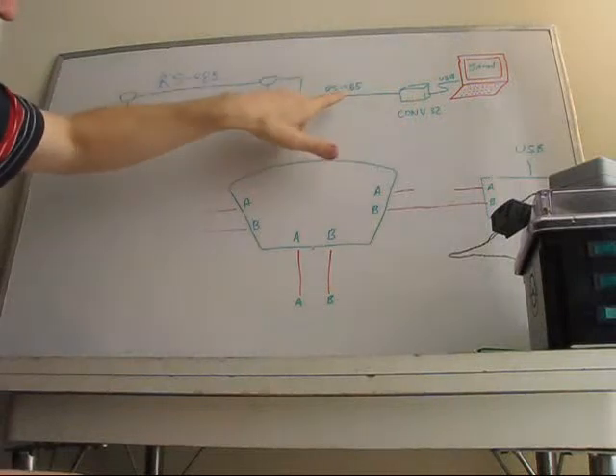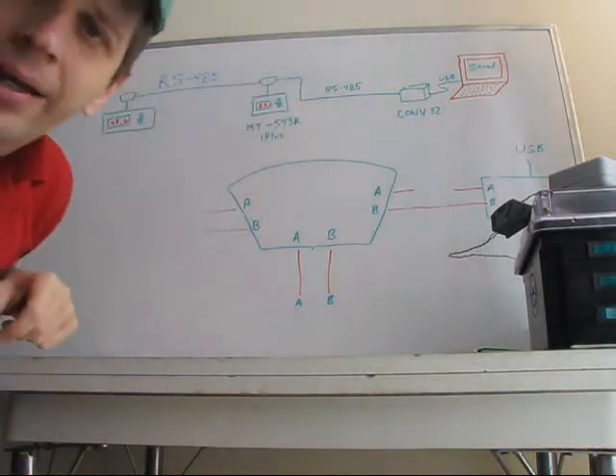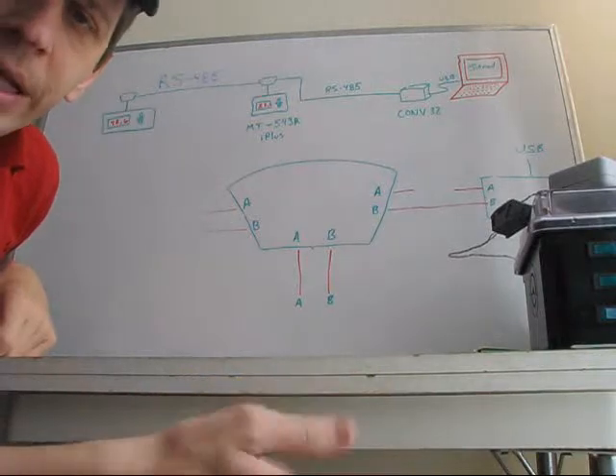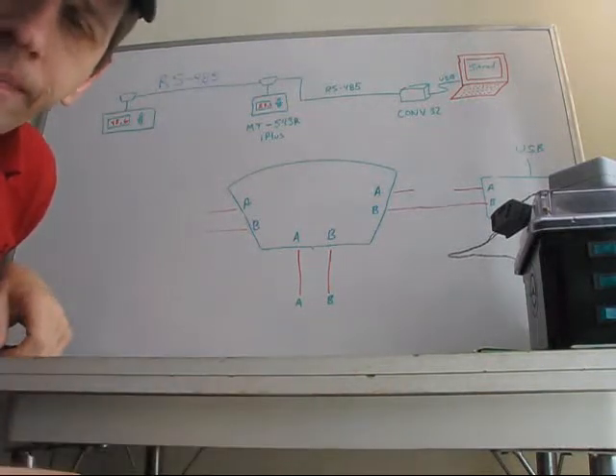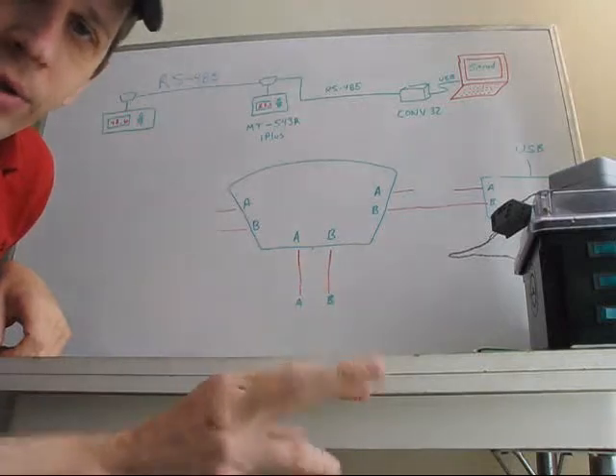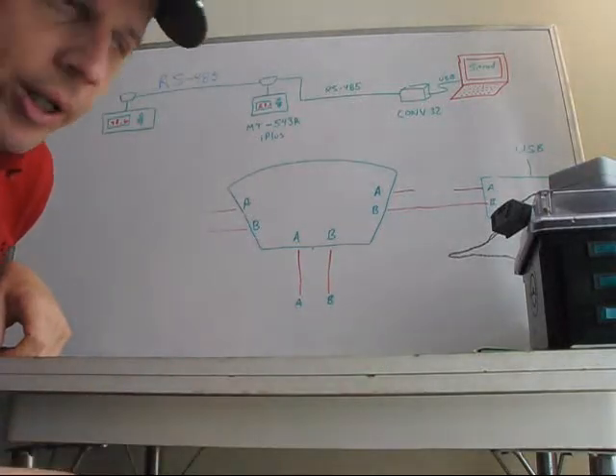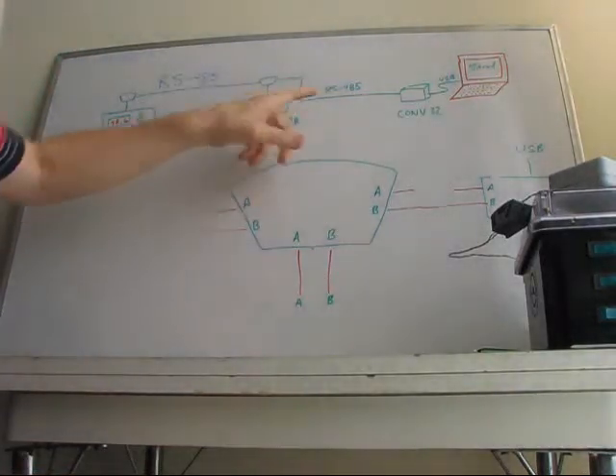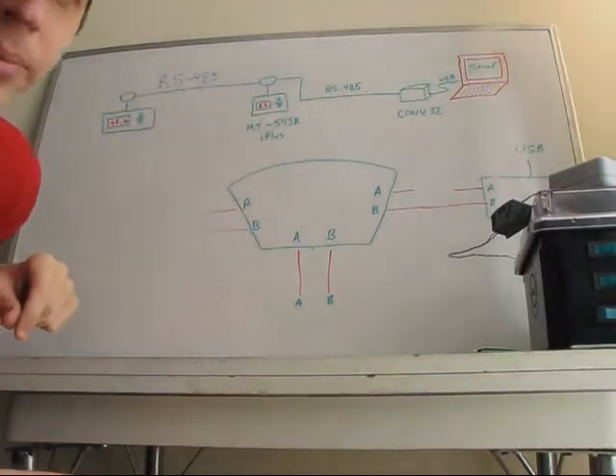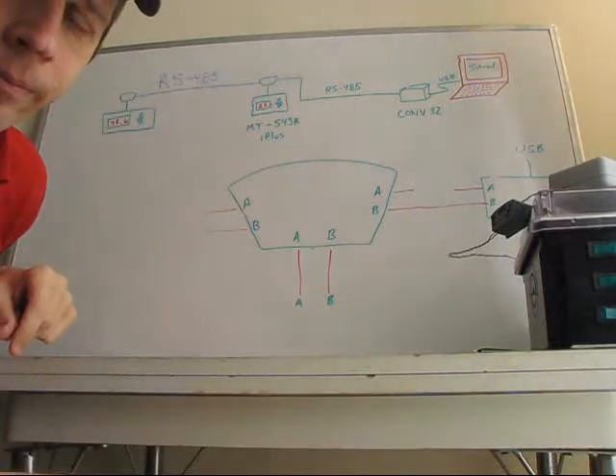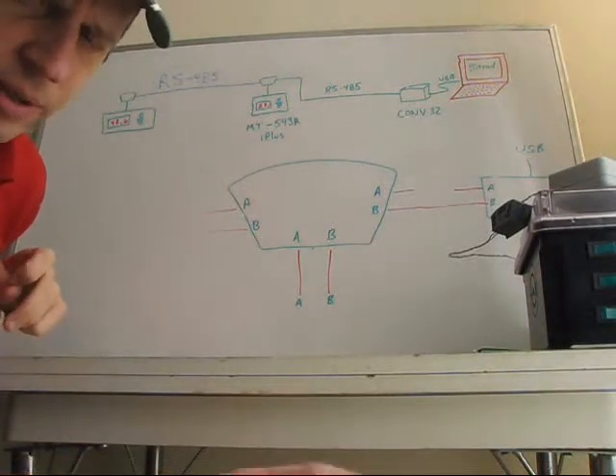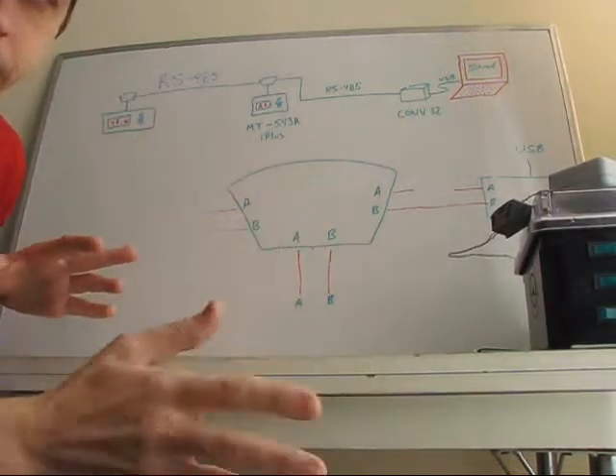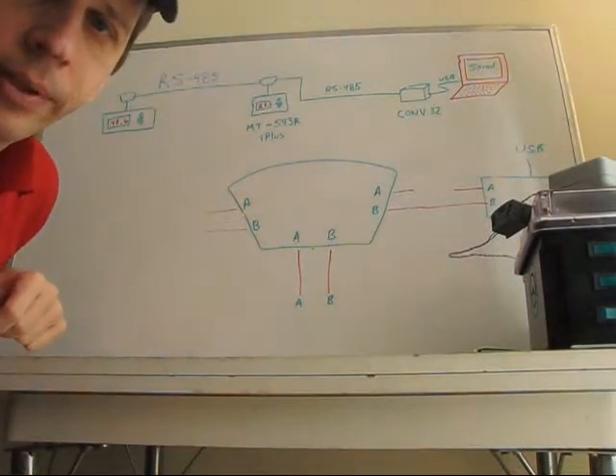So here we have the USB cable. What cable do we use here? I just took an Ethernet cable and ripped out one of the pairs that they have in there, just use that. It worked like a dream. Really fast, no problem with it. I believe you can connect via the standard RS-485 up to 256 controllers, but I'm not sure if this equipment will handle it or not. We'll talk about that in a little bit.